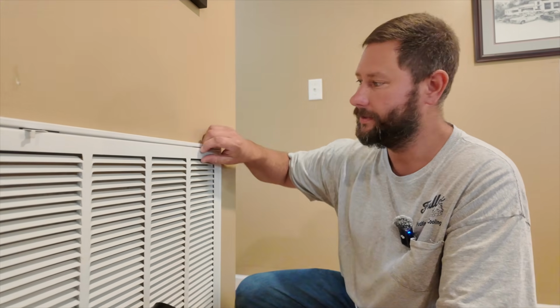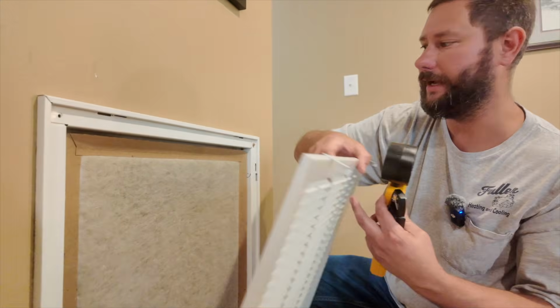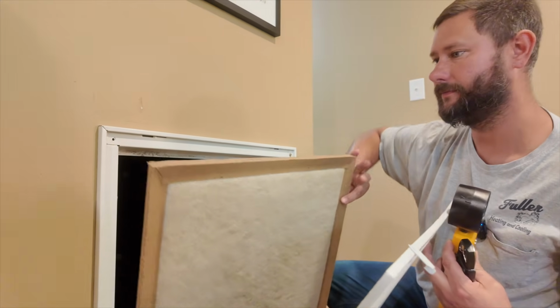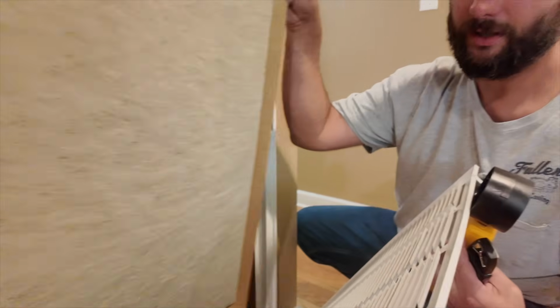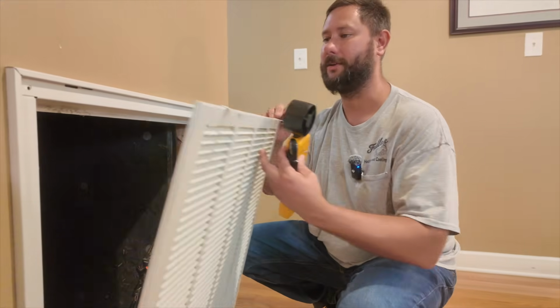To figure out the CFM, we need to take a number of readings on our return grill. Your system may have 2 return grills, it may have 1. For this system, we've only got 1 return grill, and we have to know the size. If you take out the filter, you can figure out the size, or you can take a tape measure to it. Or if you can just look at it and figure out the size, then you're probably a seasoned pro. This one right here is 20 by 30. We can take out that filter and see that it says 20 by 30 by 1. I'm going to take that filter out so I can get a more accurate reading.